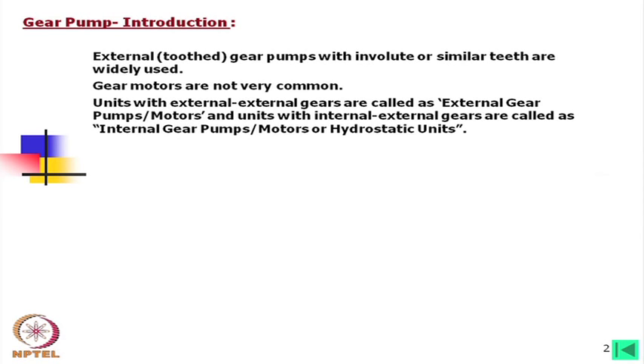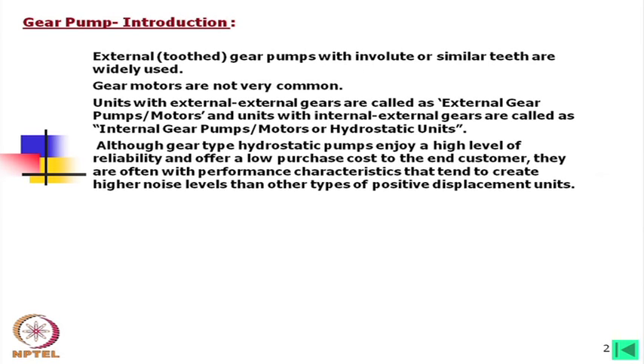You may call them external gear hydrostatic units or internal gear hydrostatic units. Although gear type hydrostatic pumps enjoy a high level of reliability and offer a low purchase and usage cost to the end customer, they are often associated with performance characteristics that tend to create higher noise levels than other types of positive displacement units.